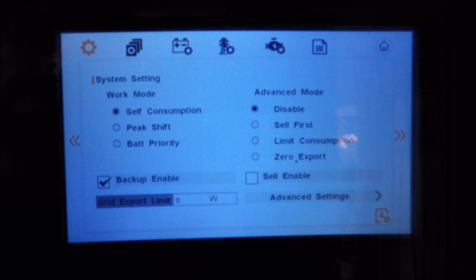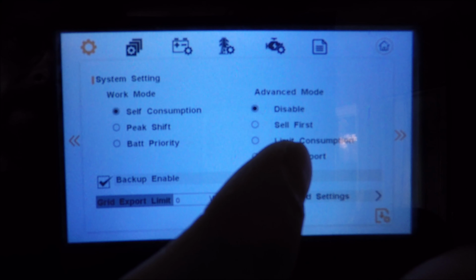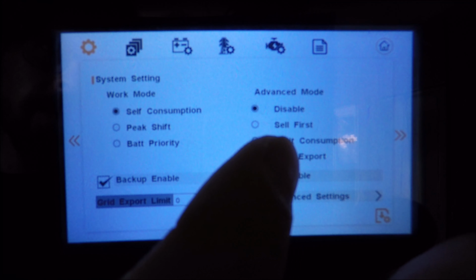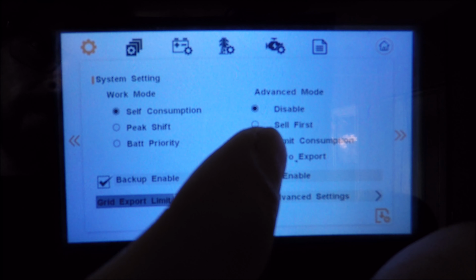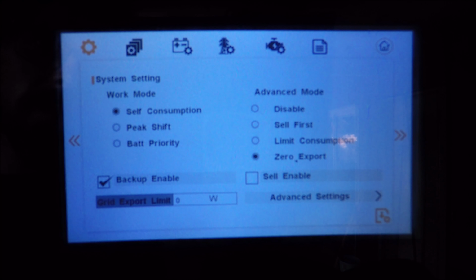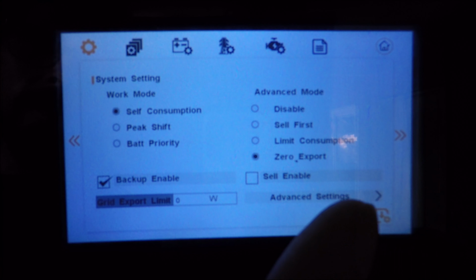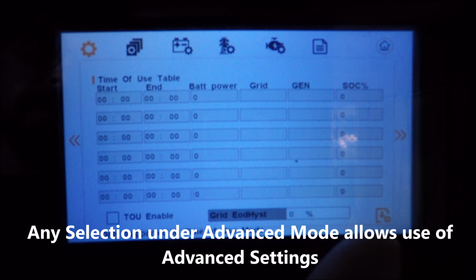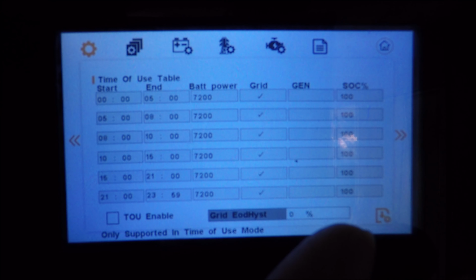Now, you always want to make sure you have a meter and you check that, but that is what zero export does. When selecting zero export, one thing to note, it is a small touch panel. If you have big fingers, you have to be careful where you touch the panel. When selecting zero export, that allows us to use advanced settings. That's where we'll find time of use and other advanced settings. We'll come back to this in a moment.